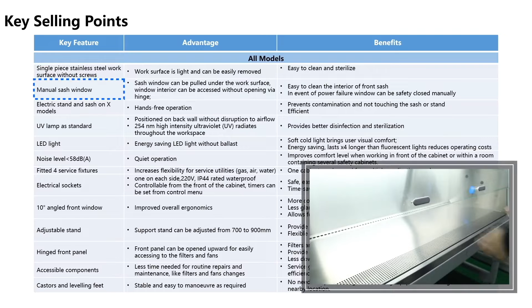Now, the electric stand and sash are great options for when you want hands-free operation. They prevent contamination and you haven't got to touch the stand, and they're very efficient products. The UV lamp is also standard on all our cabinets, and this allows for disinfection and sterilization, but it also can be programmed to turn itself on during the evening or a pre-scheduled time once the sash has been closed, and this can allow overnight the unit to be sterilized, and it's a fantastic feature.